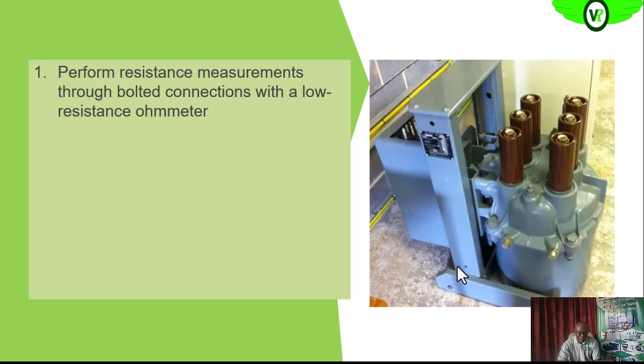So we want to perform the resistance test, and we are going to do so with the use of a low resistance meter, very low resistance, a micro-ohm or milliohm meter. So we are performing this test on bolted connections and also on the contact. Okay, so like in this case now, if this two terminal is accessible, we can close the circuit breaker and then put one of the probe here and here and measure the resistance. So that will give us the effective contact resistance.